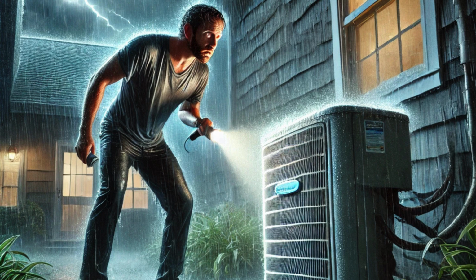I once received a call from a homeowner whose unit had frozen on a particularly hot day. Once we addressed the airflow issues and replenished the refrigerant, the problem was solved. If your coils freeze, don't keep running the system. It could lead to more severe damage.